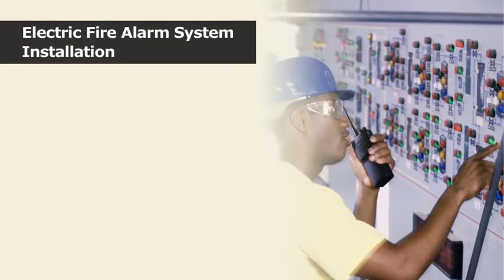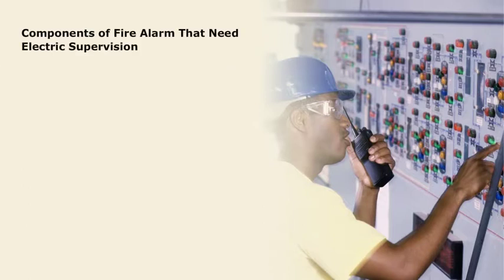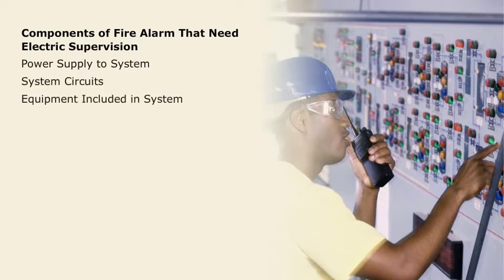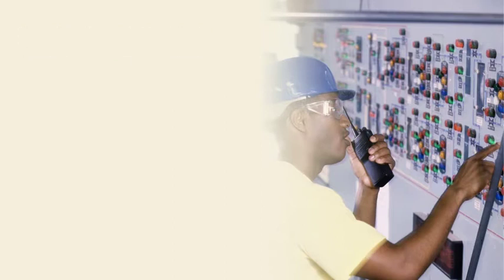The electric supervision of fire alarm systems is critical to the system operation, ensuring smooth and uninterrupted operation. Components that can be supervised include the power supply to the system, system circuits, and equipment included in the system. In this way, open circuits and ground fault conditions will activate a trouble signal.